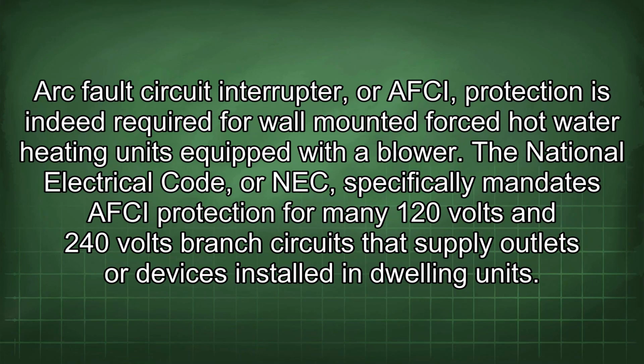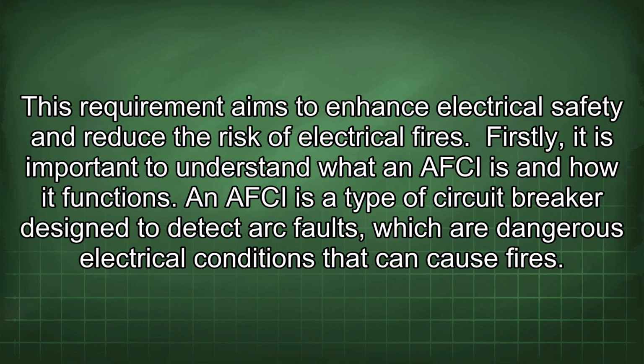Arc fault circuit interrupter, or AFCI, protection is indeed required for wall-mounted forced hot water heating units equipped with a blower. The National Electrical Code, or NEC, specifically mandates AFCI protection for many 120 volt and 240 volt branch circuits that supply outlets or devices installed in dwelling units. This requirement aims to enhance electrical safety and reduce the risk of electrical fires.